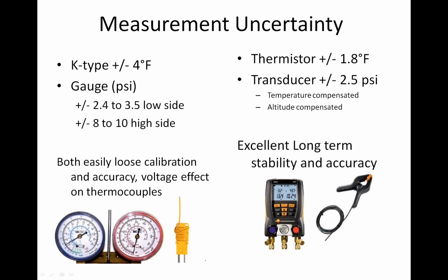And a high side, plus or minus 10, so anywhere within a 20-pound span is considered accurate, right? And then we've got a K-type thermocouple, plus or minus 4, right? So you start adding up, because you've got to remember now, to calculate superheat and subcooling, we've got to make a pressure measurement and a temperature measurement, right? So we've got to look at both halves of the equation here.